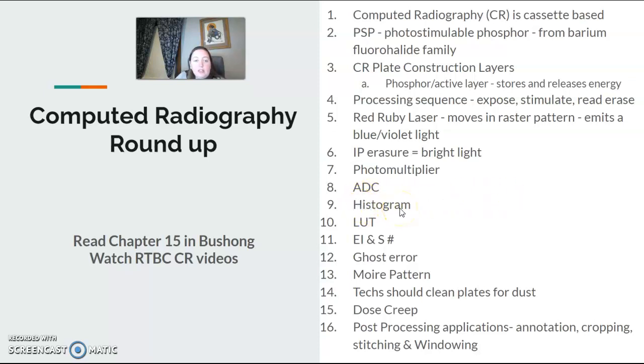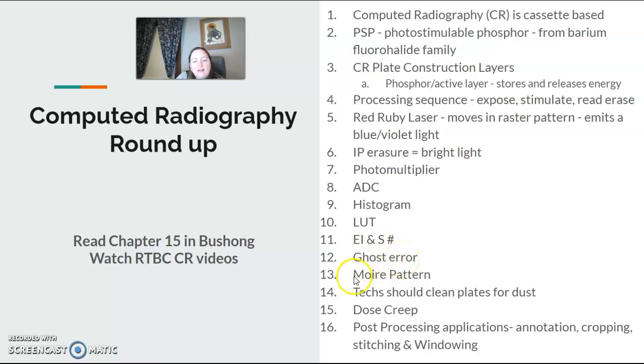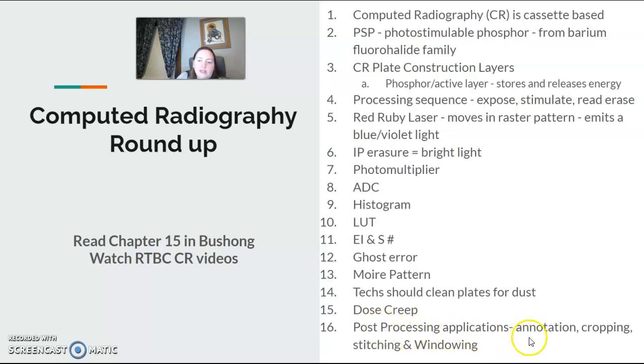The histogram is the graphical representation — the graph of each of your settings you pick on the control panel. The lookup table, or LUT, determines your digital contrast. CR cassettes use S numbers, and they're inverse. The ghost error was the erasing error. Moire pattern was the CR grid error that has the wave-like appearance. Cleaning the plates for dust is the tech's responsibility. Dose creep is an increase in technique over time — be aware of your EI numbers and ranges to prevent that. Post-processing applications to know: annotation, cropping, stitching, and windowing.